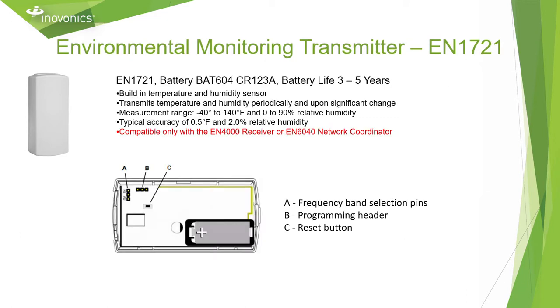The EN1721 is a built-in temperature and humidity sensor. It will send a message to its receiver periodically and any time there has been a significant change in temperature. It has a measurement range of -40 to 140 degrees Fahrenheit and a humidity range of 0 to 90%. The typical accuracy is 0.5 degrees Fahrenheit and 2% humidity, and it has a 3 to 5 year battery life.